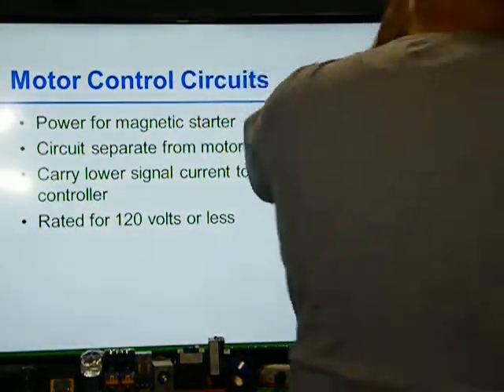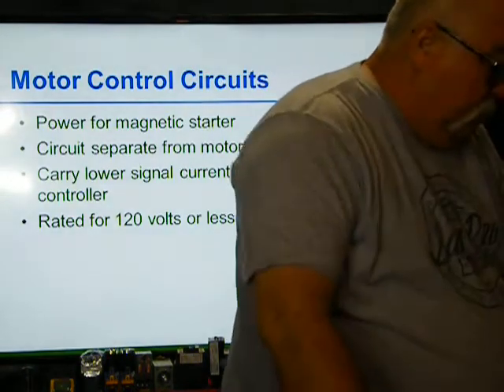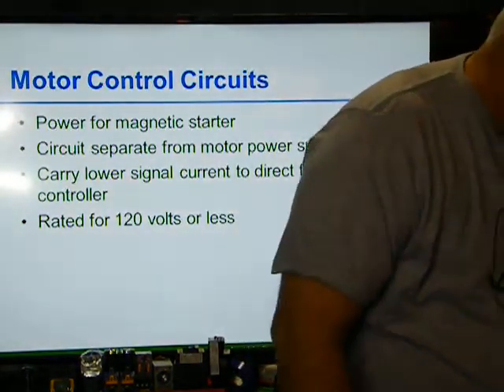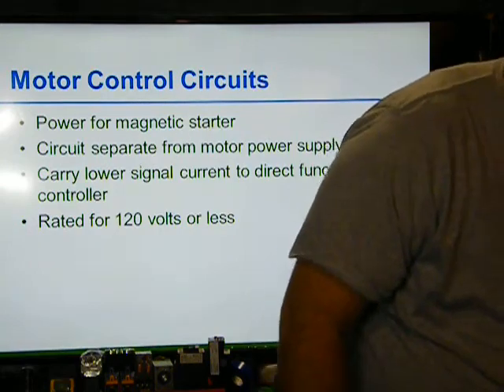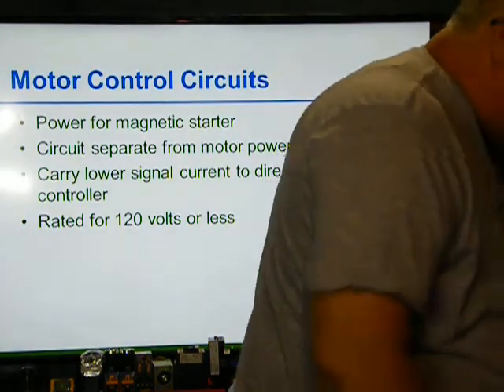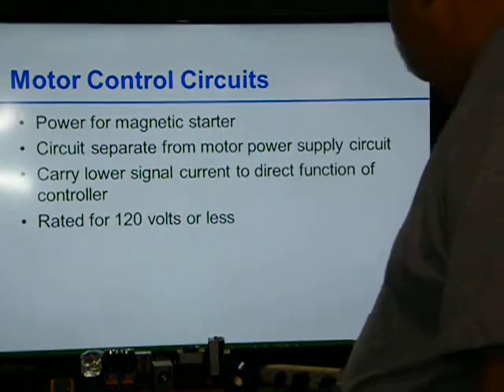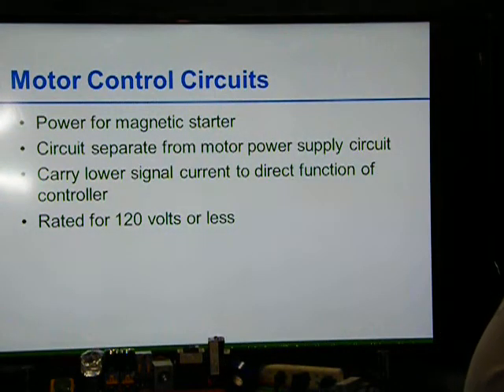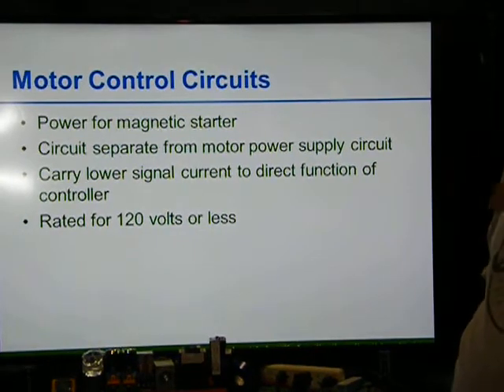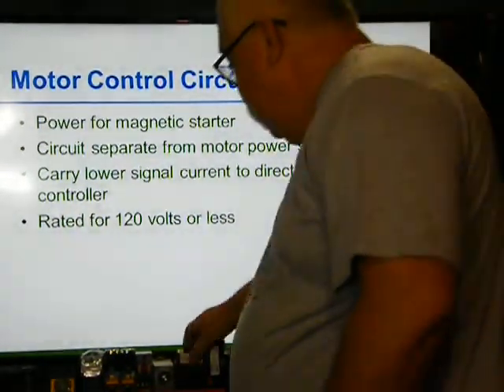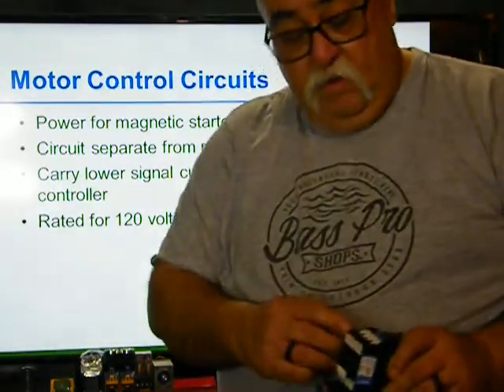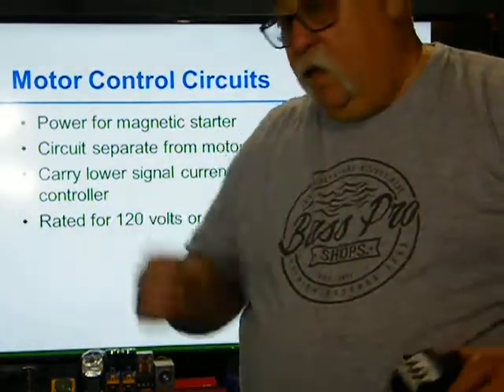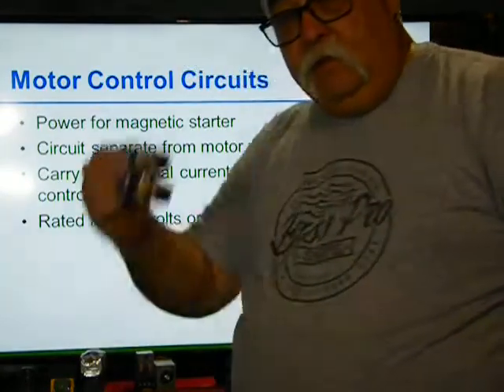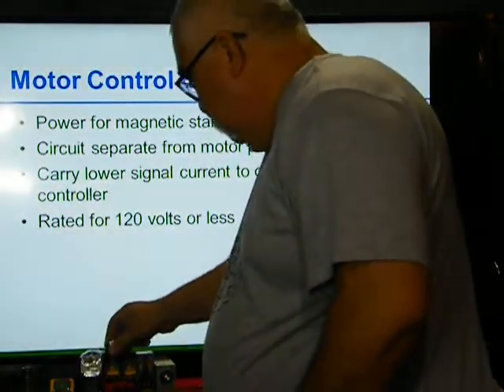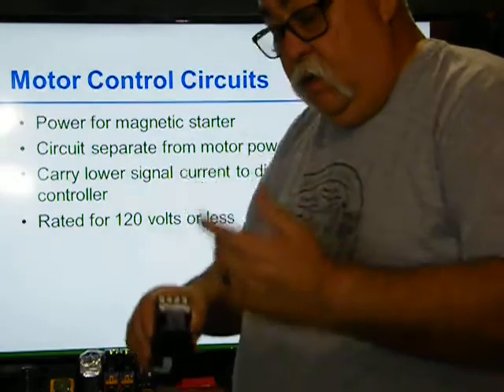We were talking last week, Thursday, about this motor control circuit, and the motor control circuit powers the magnetic starter. It can either come from the power supply with the motor. Your power comes into the relay L1. You pick up L1 and take it out to your stop-start switches, and you bring it back to your relay. Okay, that's one way of getting power.